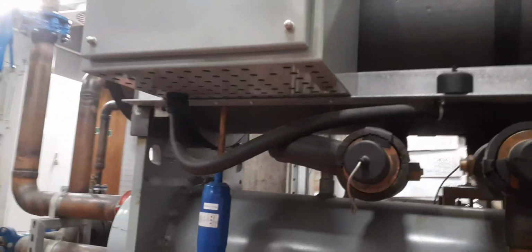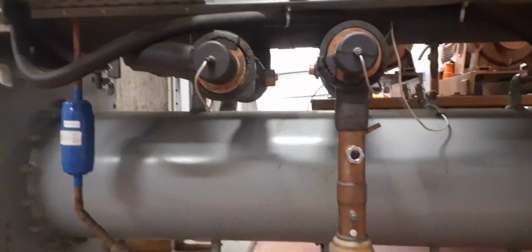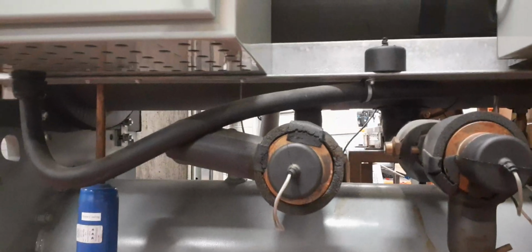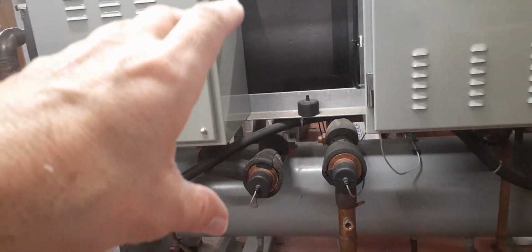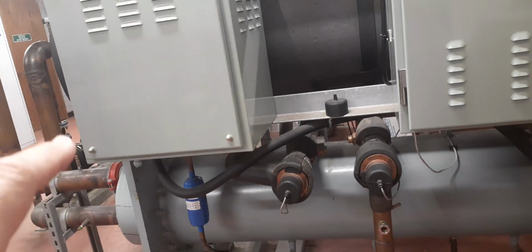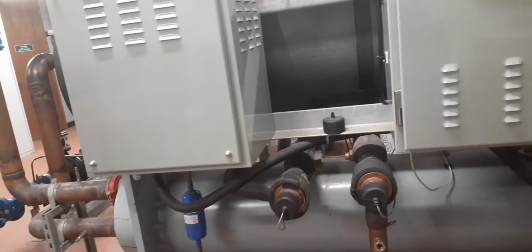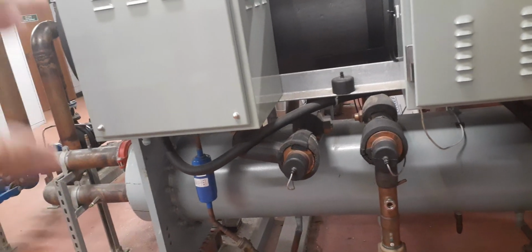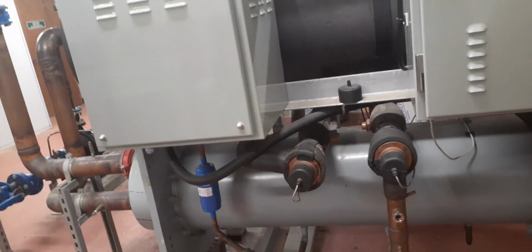So 40 degrees. Now, this particular machine, because of the metering devices, see these here? This one's actually a metering device. That one there, what's that one doing? That's coming off the bottom, so that's picking up liquid off the bottom. That's coming off the top, so that's taking gas off the top, yeah? But these here meter, and they can compensate for lower head pressure. So this machine can actually operate at a lot lower than 40 degrees condensing temperature, right? That means if you can get your head pressure down, you're going to get a much more efficient machine.